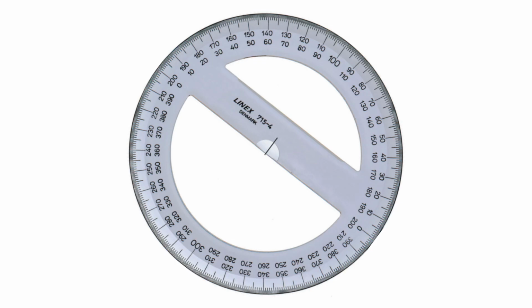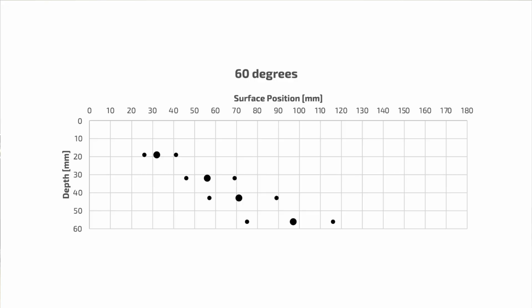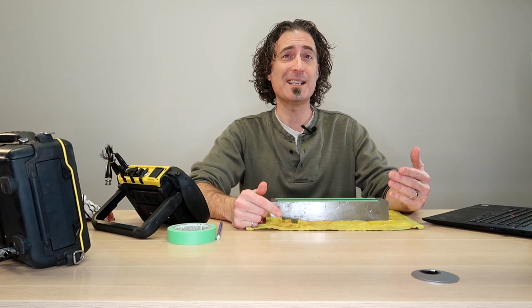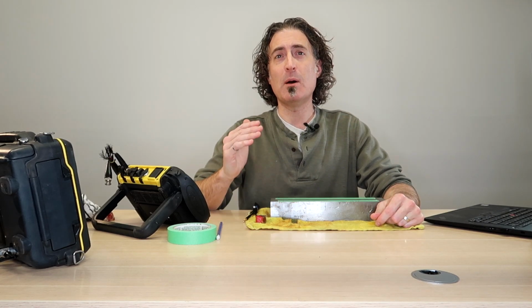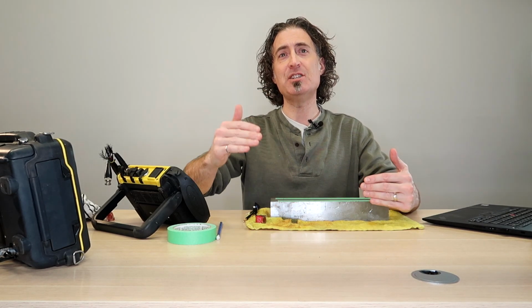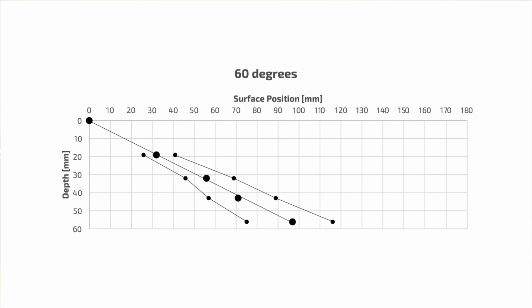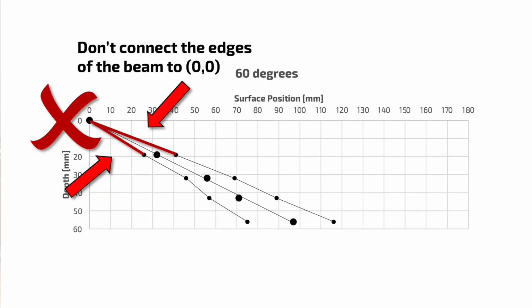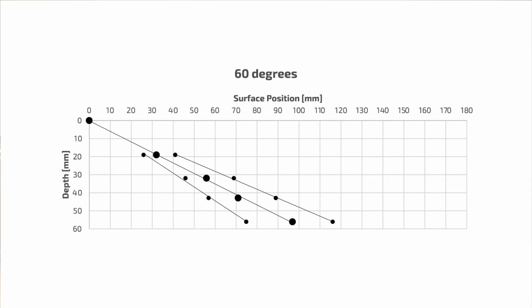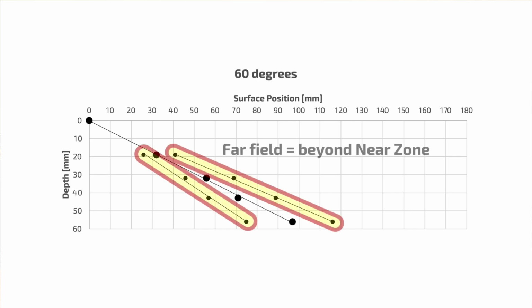Too bad we don't live on a farm. When we infer a point beyond our data set, we call that extrapolating. And we can extrapolate the center line of the beam back to the origin of the graph, or 0, 0, pretty safely. That's the beam index point. But we can't do that with the edges of the beam. The beam has some width coming out of the bottom of the probe, so it can't come to a point. As well, if you want to draw a straight line between data points instead of just playing connect the dots, that's fine too. But do that only on the points in the far field.